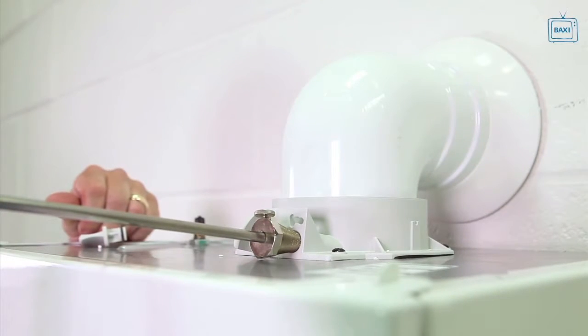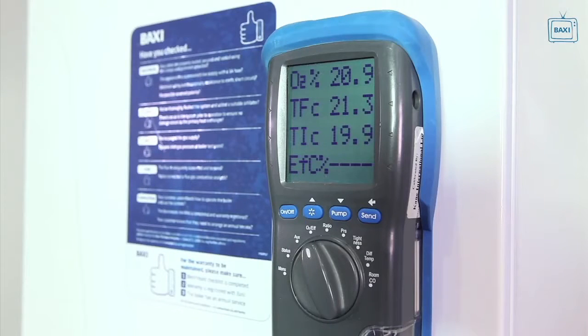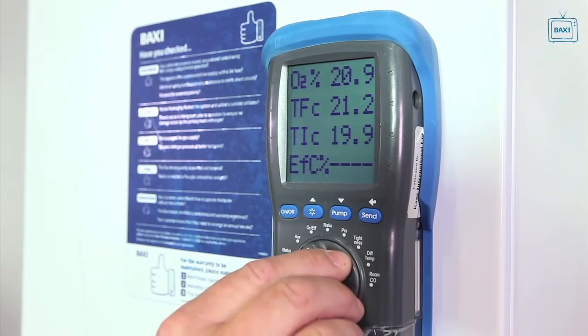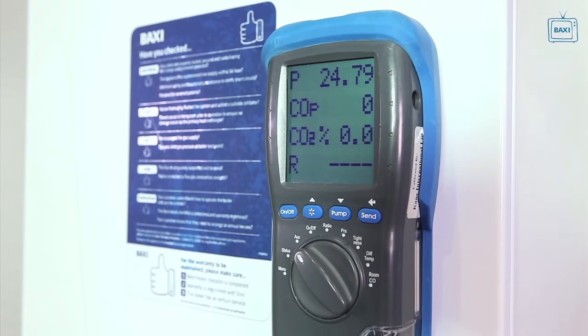Carry out the flue integrity combustion check by inserting the analyzer probe into the air inlet testing point, allowing the reading to stabilise. A positive check will show a reading of oxygen equal to or greater than 20.6% and carbon dioxide at less than 0.2%.